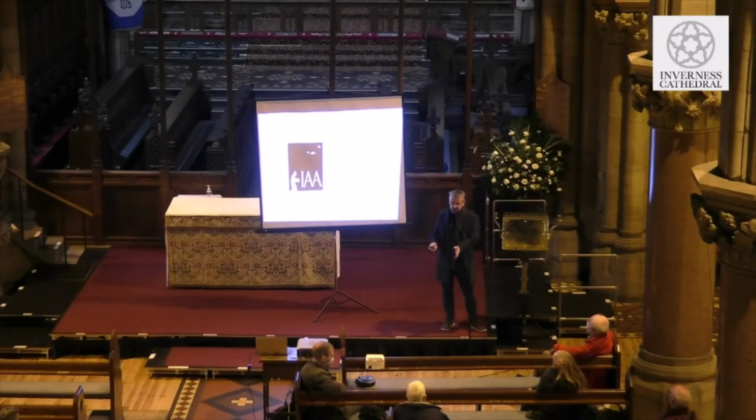So that's just in the water tank. Then there's the issue that you need slightly bigger radiators. And then there's the issue of balancing that with your ventilation and your building fabric. If you can recall the slide that I showed you in terms of where all the energy goes, the pie chart, one of the biggest issues you're going to have is air infiltration. And that's one of the things that we are trying to tackle in the cathedral itself. Because we can insulate these, well, we can't because it's a Grade A listed building, but if we could insulate these buildings and throw as much insulation at it as we could, it's only going to give the smallest dent in our carbon emissions, because we're losing so much air through the floorboards.